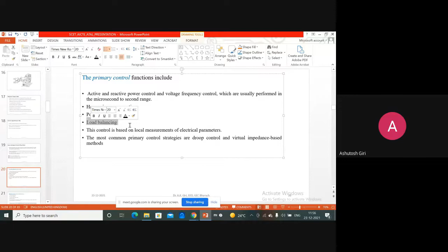That's why these are the things coming under the primary control issues, and they can be solved by control algorithms or control techniques which will be implemented at the device level, right? Keep in mind, primary control means we are developing everything for a particular device. Suppose there are two inverters, you have to use two primary controls. This control is based on local measurement of the electrical parameters. Suppose load current you can measure and feed to the control system, supply current, generator current, grid is not there, compensator current, all these things can be measured locally and control parameters can be adjusted accordingly.